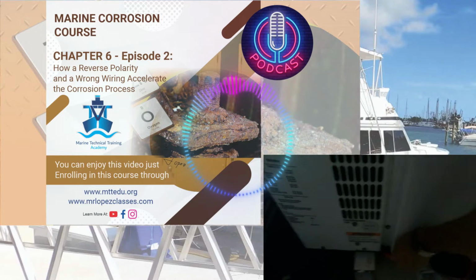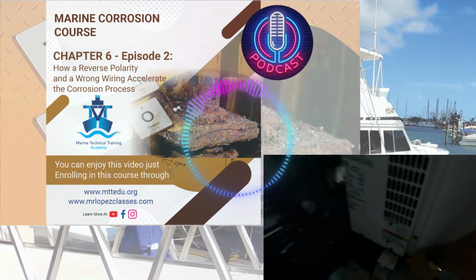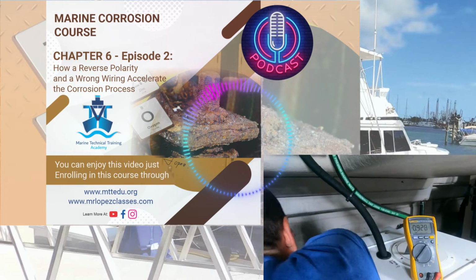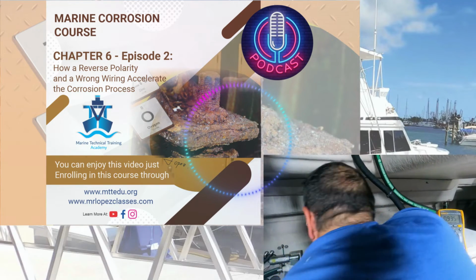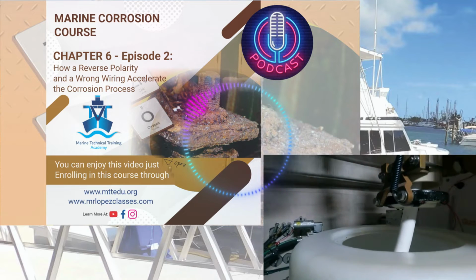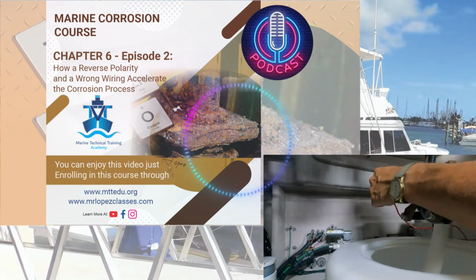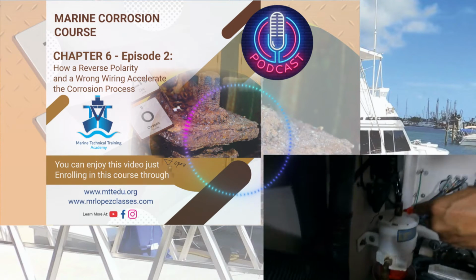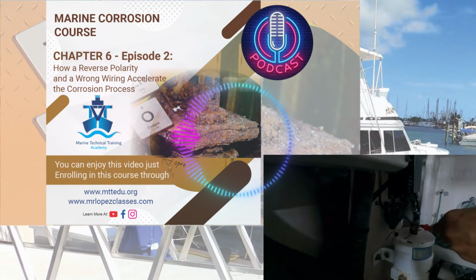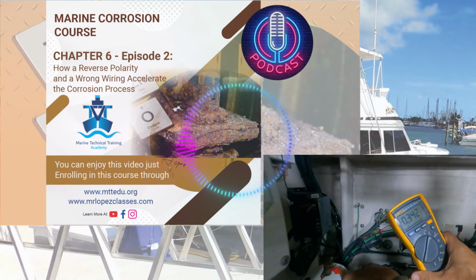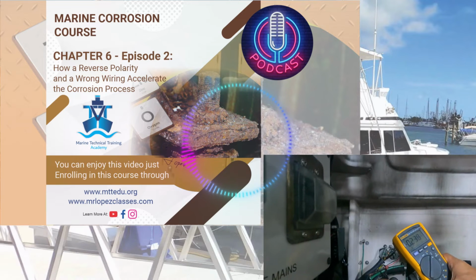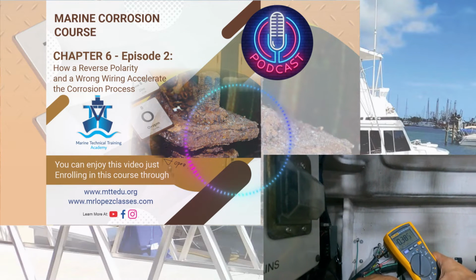You have that constant amount of current, 2 amps, 3 amps, 5 amps, moving through the bonding system constantly, 24 hours. This is catastrophic. Once again, you have two chances. A wrong connection on the panel, the hot enters into the neutral and the neutral into the hot. This is one possibility.